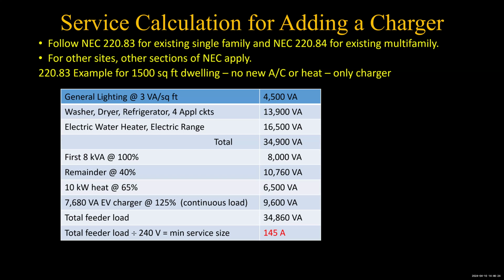and you have to add that in at 125% of its rated load because the assumption is it will be charging continuously, which means you almost have to have more than one vehicle because continuous means charging for 3 hours. And if it only takes an hour or 2 hours, then that isn't continuous. In that case, a 40 amp charger needs a 50 amp circuit breaker. All right, so you have to add that in at 9600 volt amps to all the rest of this, just like you did for the heat or the air conditioning.